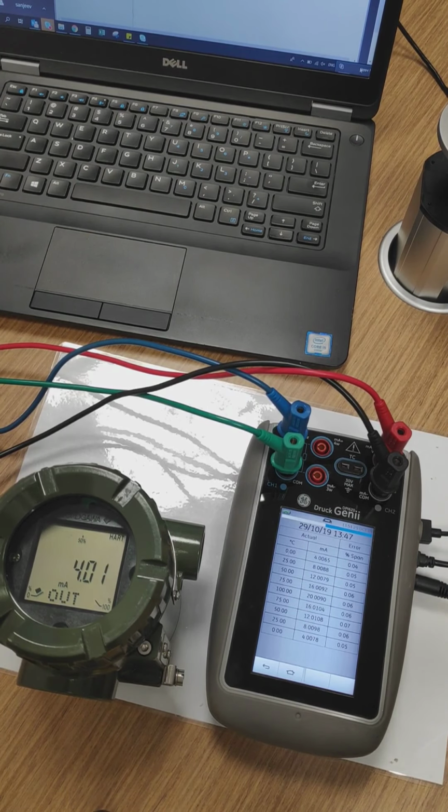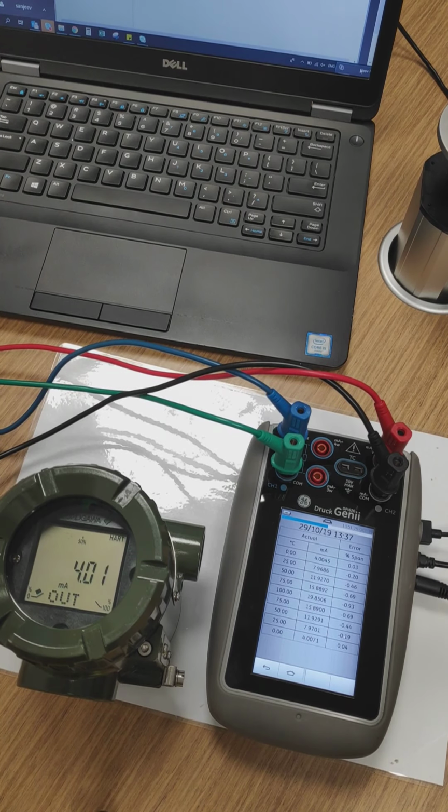Everything is done automatically here thanks to Foresight combined with the Genii. See, the error here is relatively large compared to what we used to have, and that was because of a 1% only error. So instead of 100 degrees it was 101, and this shows us how critical calibration is for the instrumentation and the decisions taken from it.